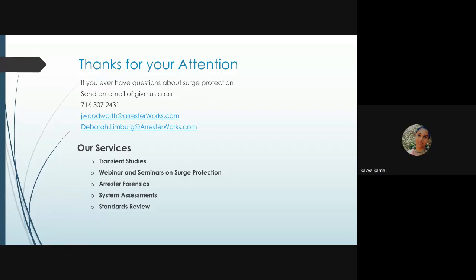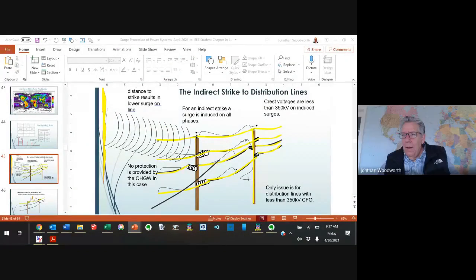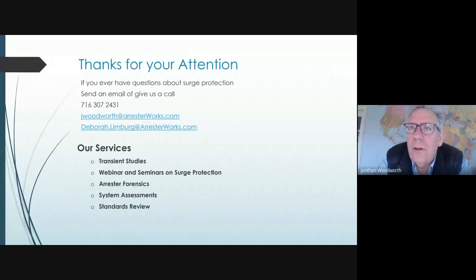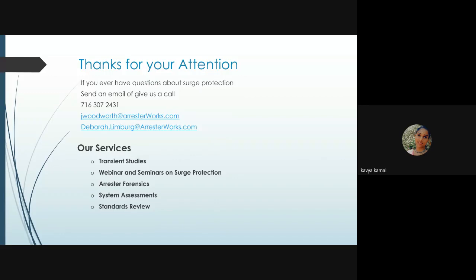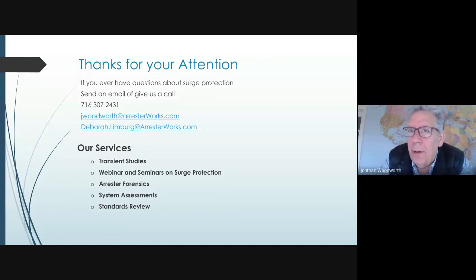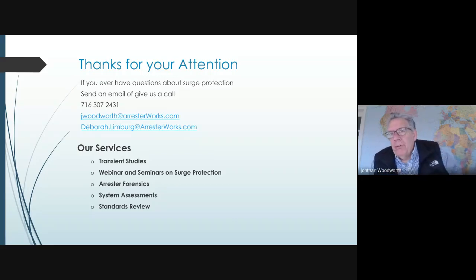Where do surge powers come from apart from lightning? The only place surges come from apart from lightning would be from breakers. Well, not the only. Let me give you a few examples. When a breaker operates, it'll generate a switching surge. If a higher voltage line falls on a lower voltage line, that generates a very high surge on a system. So it's where two systems of different voltage touch each other. Sometimes a car will hit a pole and the line will drop to the ground, and you can get a surge from that, from a line drop. That's about it.